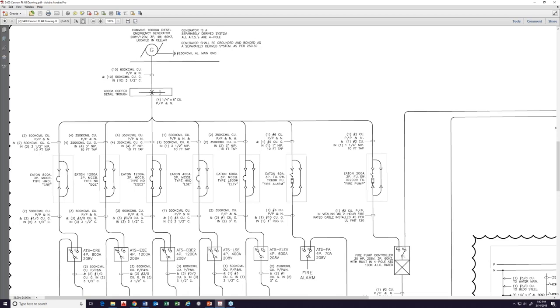This happens to be a nursing home where we have different types of emergency loads. NFPA 99 requires what's called an EES type, an essential electrical system, and there are different requirements on how you must have separation of devices and feeders and ATSs, and a lot of other things to consider. So from a reliability perspective, and saving some money and getting the job done right, this is a very good way of doing it. And yes, you can put a simple disconnect without fuses, and it will still comply with that requirement that you must have a disconnect at the generator.